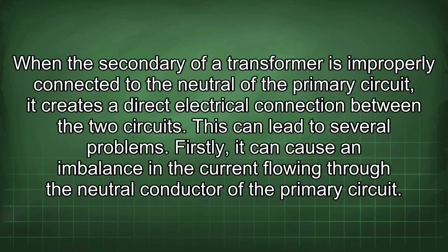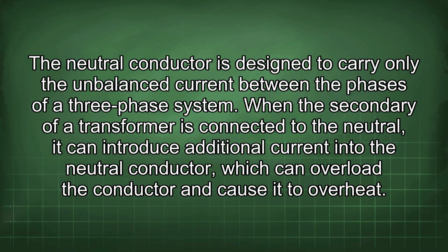When the secondary of a transformer is improperly connected to the neutral of the primary circuit, it creates a direct electrical connection between the two circuits. This can lead to several problems. Firstly, it can cause an imbalance in the current flowing through the neutral conductor of the primary circuit. The neutral conductor is designed to carry only the unbalanced current between the phases of a 3-phase system. When the secondary of a transformer is connected to the neutral, it can introduce additional current into the neutral conductor, which can overload the conductor and cause it to overheat.